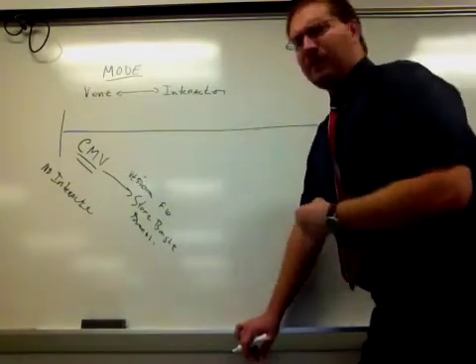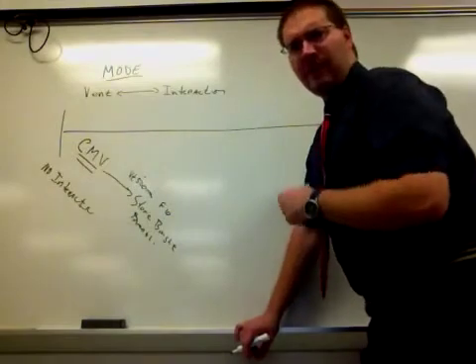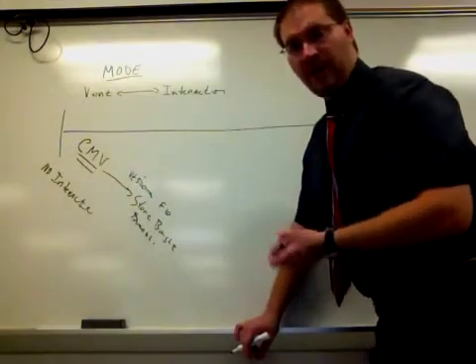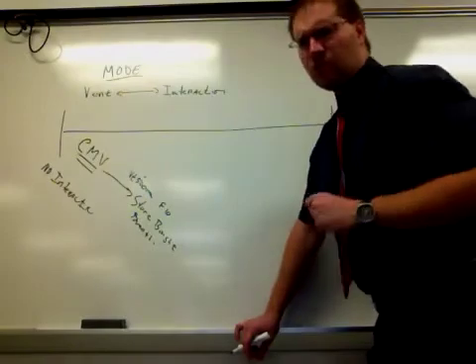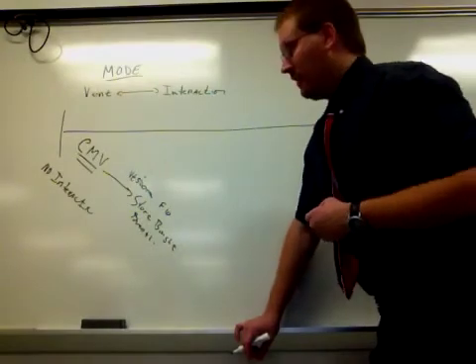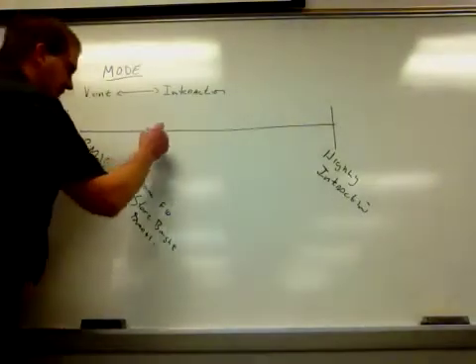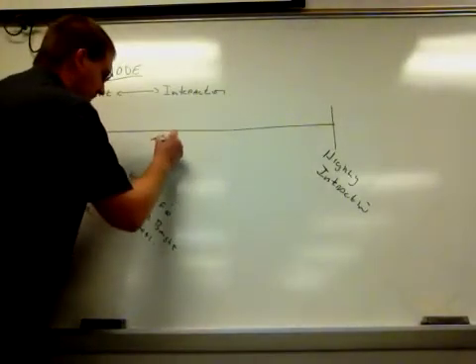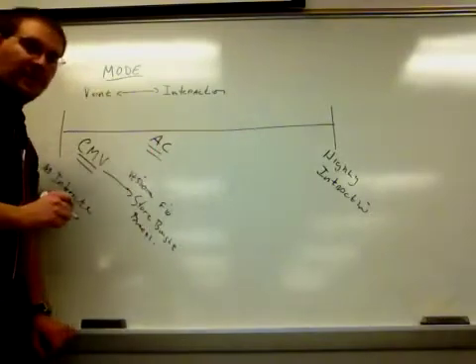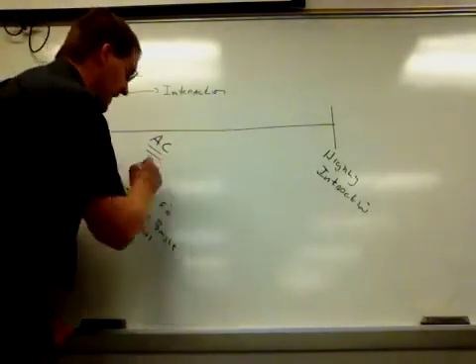You will typically see CMV in certain types of transport ventilators and certain anesthesia machines will run in CMV. So let's go ahead and step up an interaction here. We'll step up to the next mode that is seen fairly commonly, and that's assist control or AC.